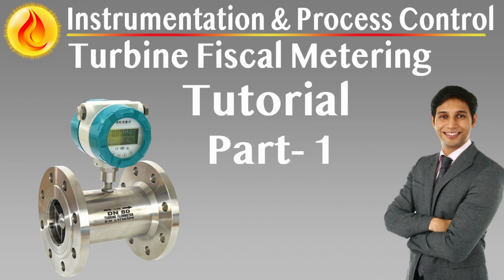A comprehensive escalation procedure must be defined for when these limits are exceeded, triggering revalidation, recalibration, and notification to stakeholders and regulatory bodies. Defining system-wide deviation boundaries. In addition to per-instrument thresholds, the entire measurement system must have a maximum allowable deviation defined for averaged yearly flow rates. This overall limit ensures that minor instrument drifts do not aggregate into unacceptable fiscal errors.